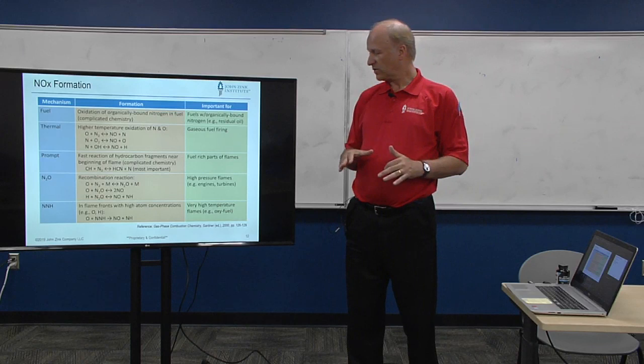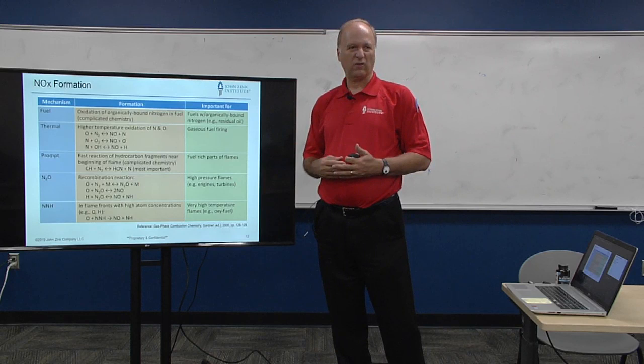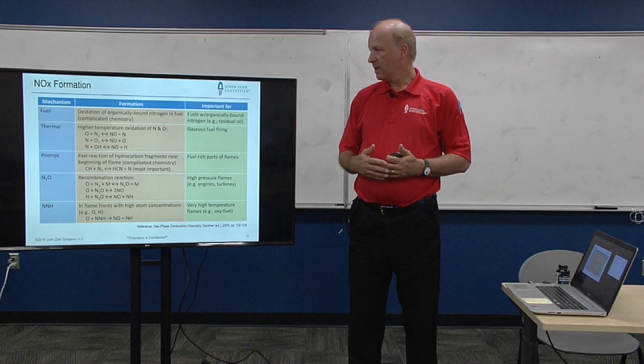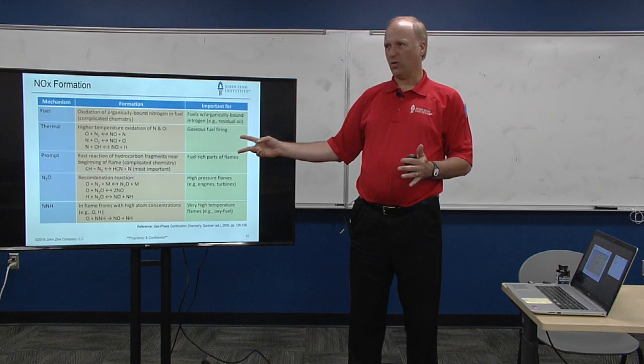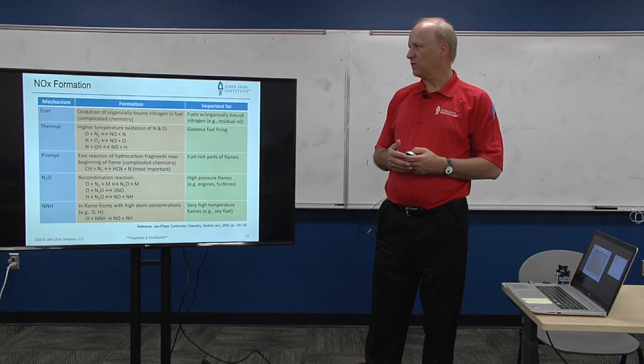For most gaseous flames, the thermal and prompt NOx mechanisms are the only ones of significance. We're going to talk a lot about thermal NOx today because we can control things related to temperature, and that will help us reduce NOx. There are some operating parameters that have a significant impact on NOx. The first one is furnace temperature — this is not something we can normally control, because the furnace must be at a certain temperature for production. But furnaces that run hotter are probably going to make more NOx.